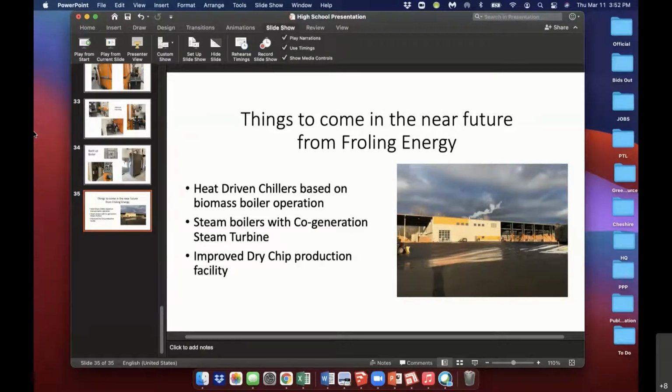Yeah, okay, good. So the sizing in general, of course, can be done in many different ways. And I will go through a little bit of the history because it really does boil down to the longevity of the boiler and operation of the boiler as well. So when I started first installing biomass boilers in 2008, so a little while ago, we tried to be really fiscally responsible and really undersize the biomass boilers and then put larger backup boilers in order to basically stretch the dollar as far as possible.